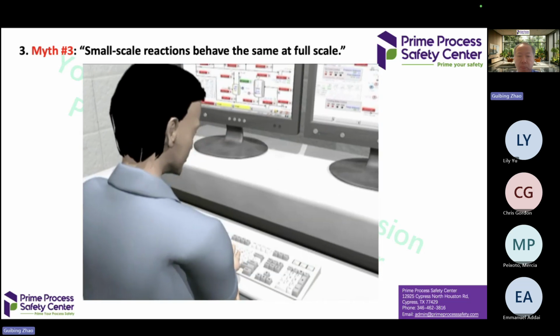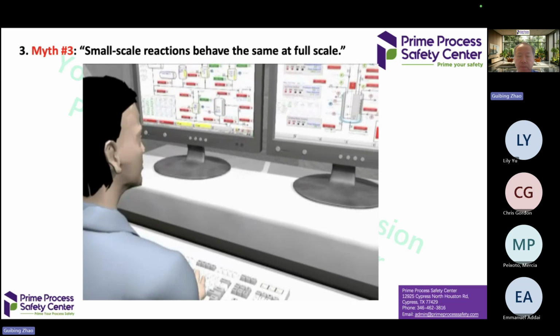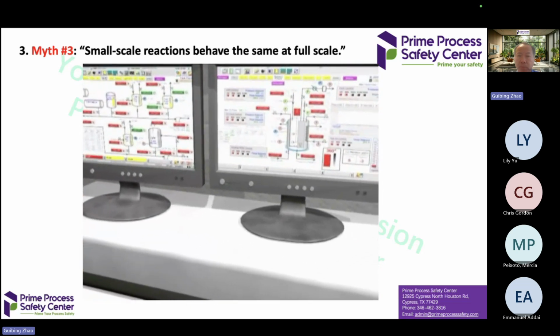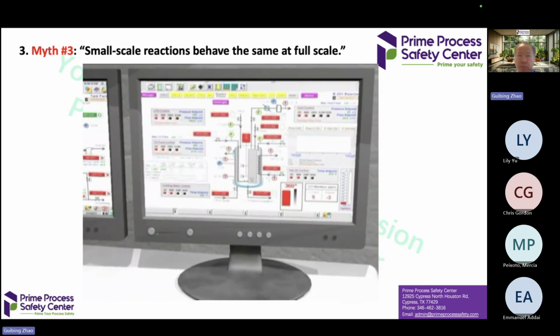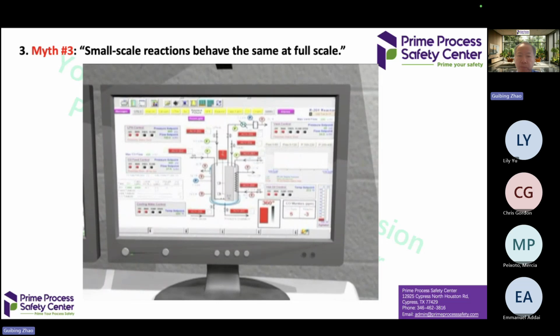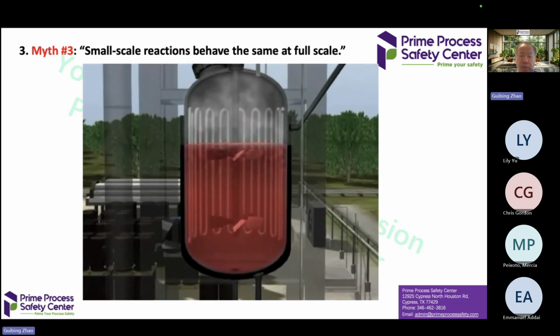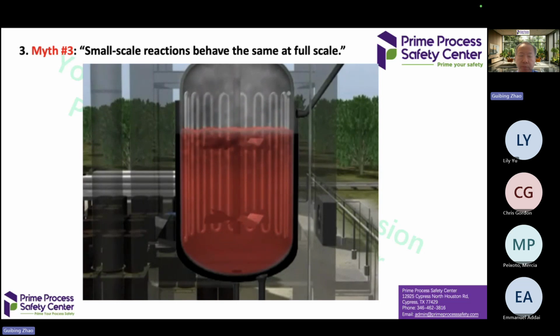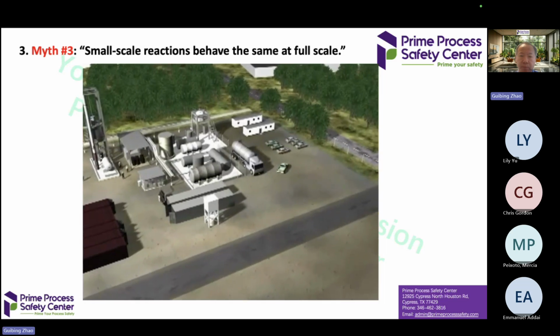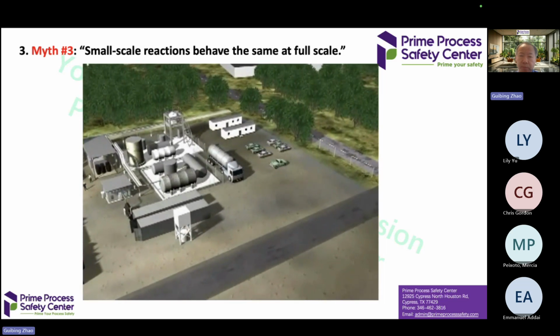However, on the day of the accident, the CSB found that the operator tried to cool the reactor as usual, but the cooling system likely malfunctioned, perhaps due to a blockage in the water supply piping or a valve failure. The temperature and pressure inside the reactor began to rise uncontrollably in a runaway chemical reaction. T2's co-owners returned to the plant after a worker called to report the cooling problem.